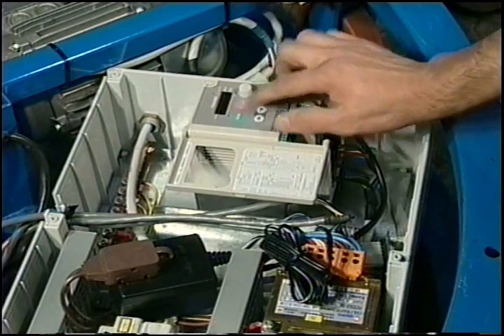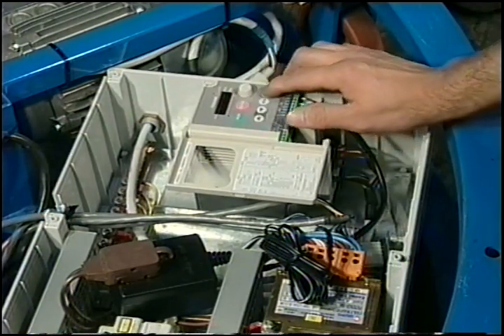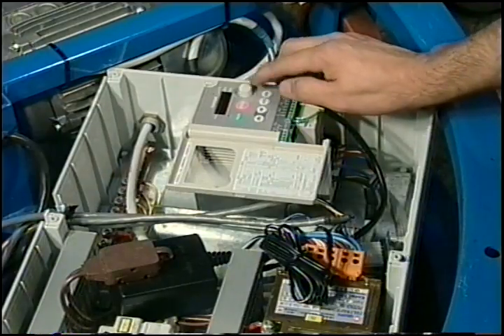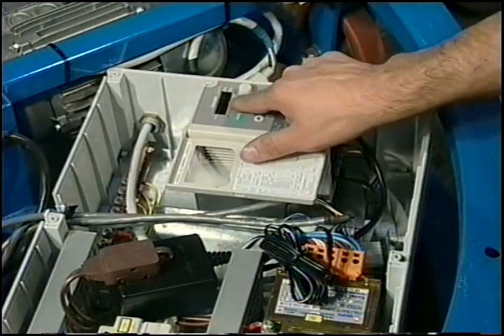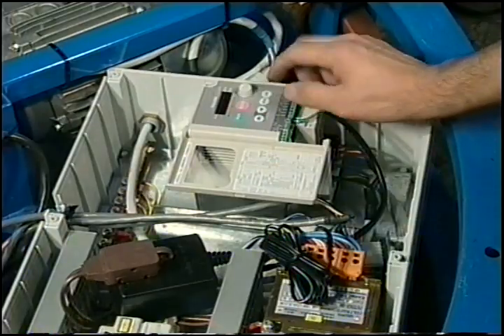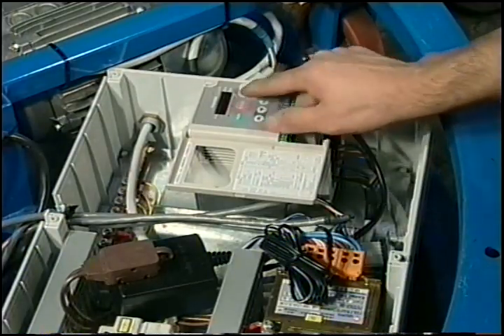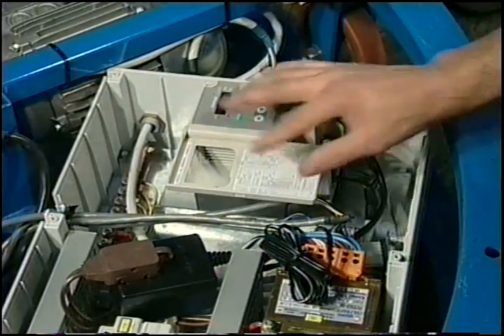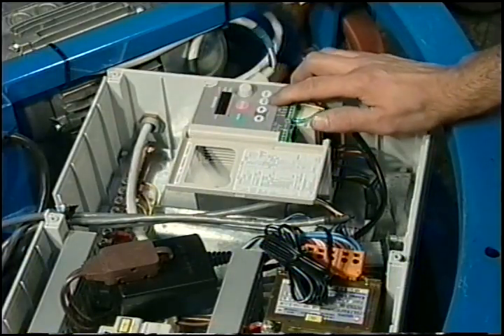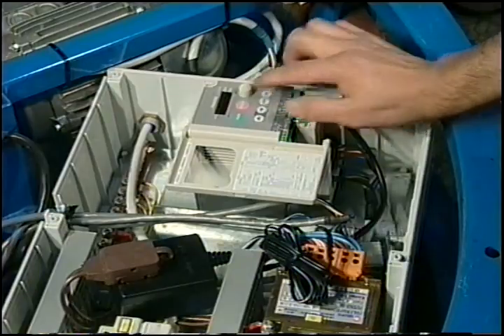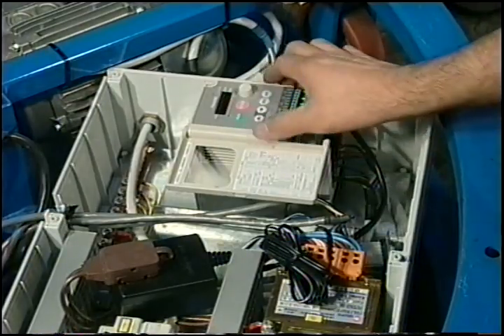Hit enter. Display is going to flash. It's accepted your command. You want to just verify that by hitting enter again. You should still have the value of 0. Then hit enter again. It's going to go to the next parameter. Then to get out of the test screen, you just hit the MON button until you're back at 0.0, which is your normal operating screen.